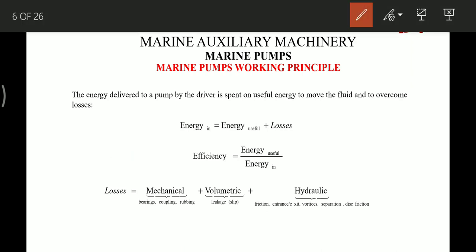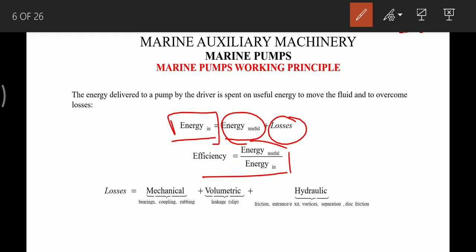The total energy supplied to the motor equals the energy used by the pump plus the energy used in overcoming losses. The efficiency of the pump system is the useful energy divided by the energy consumed by the motor. Losses are of three types: mechanical losses due to bearings, coupling, or rubbing; volumetric losses due to leakage; and hydraulic losses due to friction, vortex separation, or disc friction.